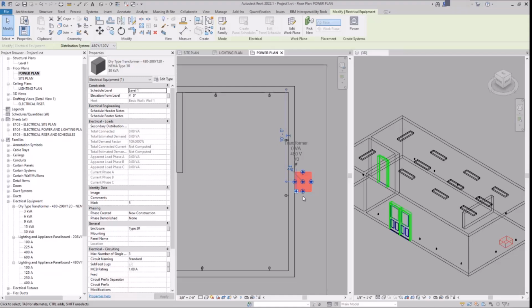And this is more of a question. Anytime it's 3-phase, even if it's 480/277, you still have to use the 480 number to find the amps. Correct? There's also the, what'd you say, 208?